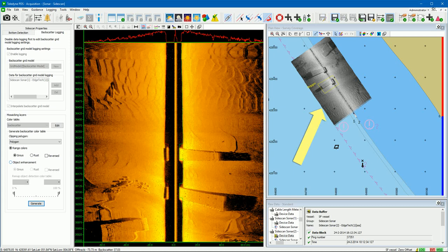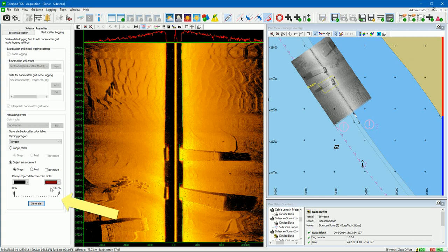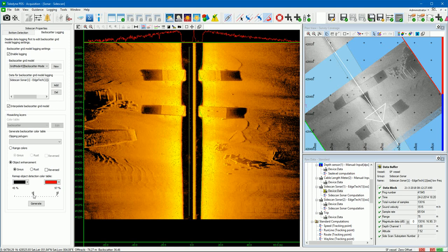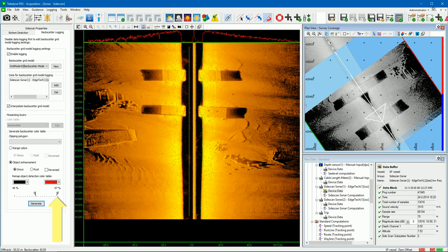The colors of the mosaicing are now based on the intensities of the selected polygon. By using the object enhancement feature, it is possible to color detections of a certain intensity level, making features based on a selected intensity more visible. Select the color and set the intensity level percentages by moving the slider. For example, to visualize shadows more clearly in the mosaic, turn on object enhancement and set the level of intensities to be colored black. All intensities lower than the set level are now colored black — in our case the shadows are now more clearly visualized. The same can be done to see detections more clearly; move the right slider to specify the intensity you want to color red.